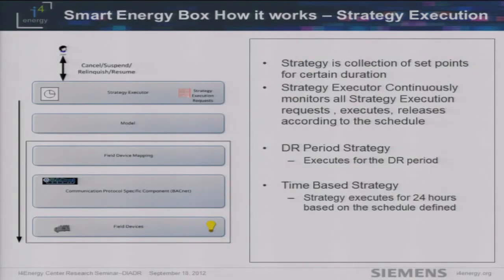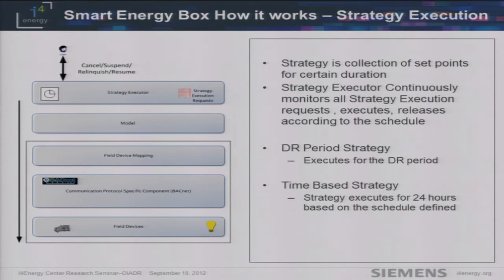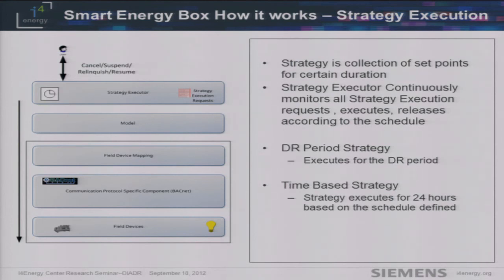The strategy executor continuously monitors the current time and executes onto the building. The way we model the building information is protocol-agnostic — we define the model and map it to building control points according to the protocol. For example, thermostat room 64 is mapped to a BACnet point with corresponding information. If you want to adapt to a different protocol, you don't need to change any components inside the box — you just map to a new data point and write the new adapter. For a SOAP point, map thermostat 64 to the SOAP point, write the SOAP adapter into the Smart Energy Box, and it works automatically.